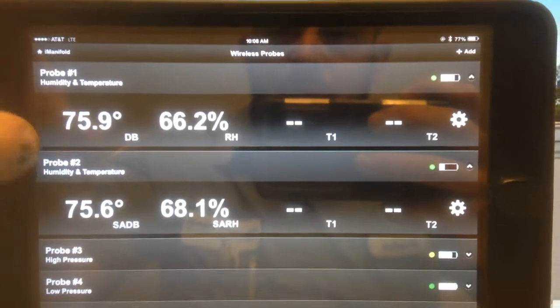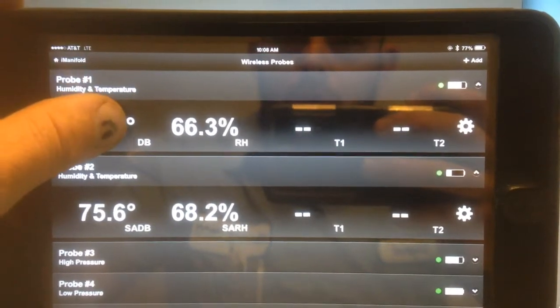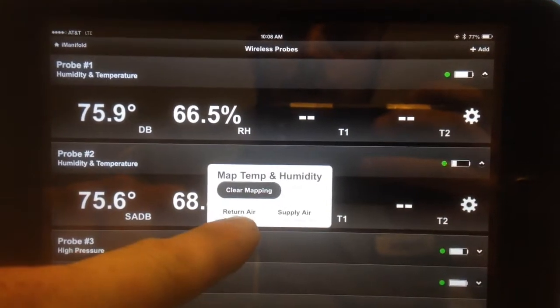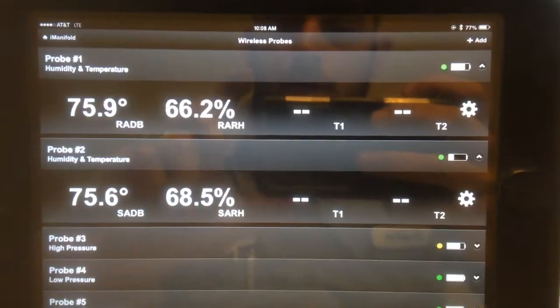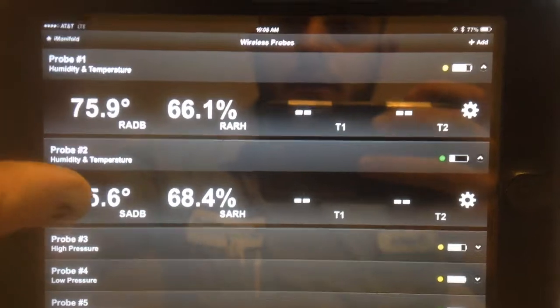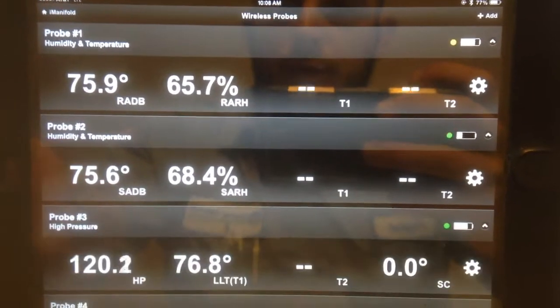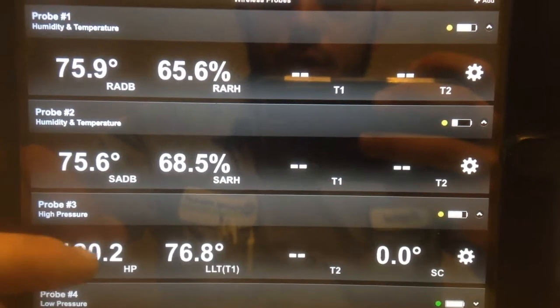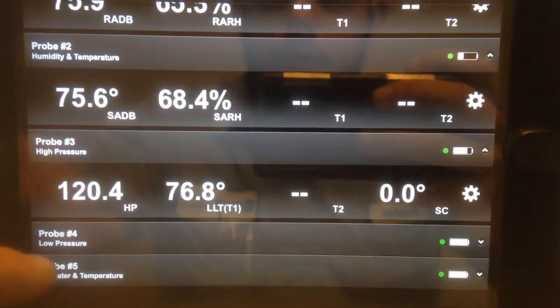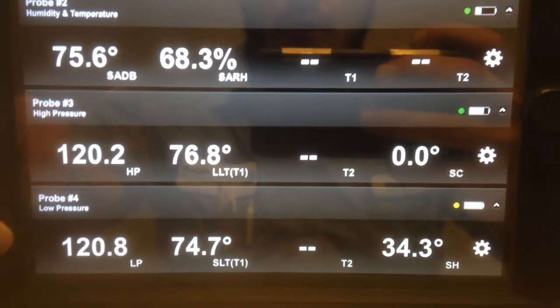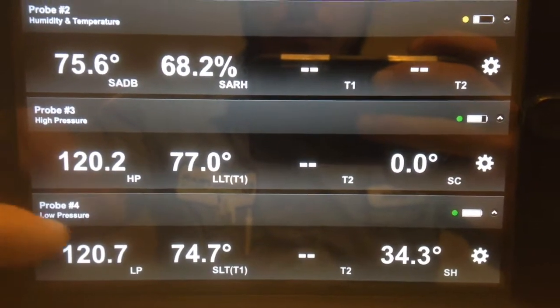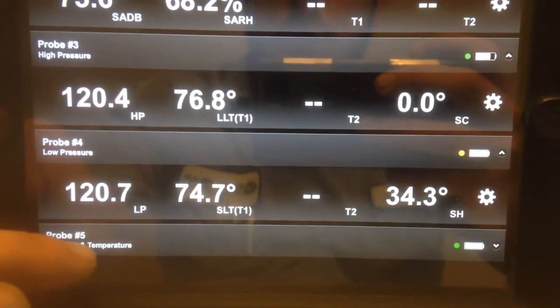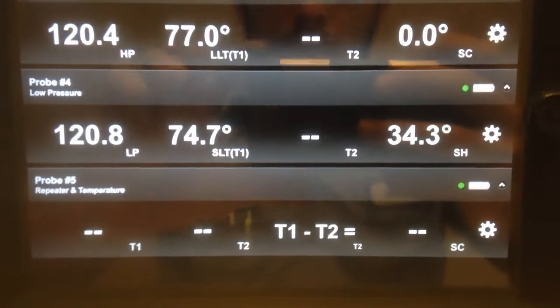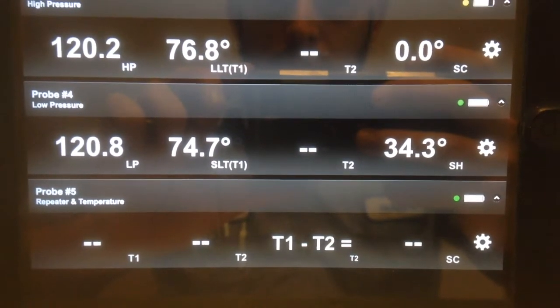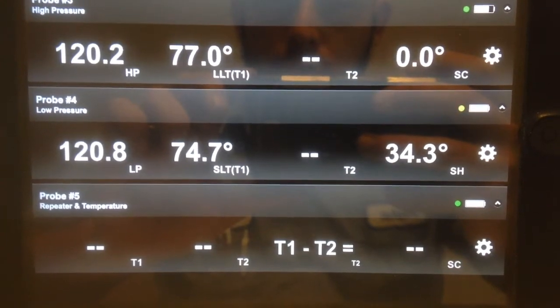Probe 1 is temperature and humidity. Probe 2 is supply air temperature and humidity. We are going to map this one since it's not mapped. Return air. It's that easy, guys, to map them. Probe 3, we've got high pressure and liquid line temperature. Probe 4, we've got low pressure and suction line temperature, as well as superheat. And the repeater probe displays no information because nothing is connected to T1 and T2.